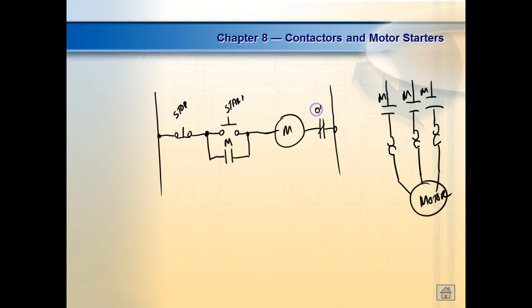And this right here would just be labeled OL for overload. So these sensors are what's controlling this contact right here. So I come up here, I start this thing, right? I press the start button, it seals in, the motor comes up and runs, right? And then if we get an overload, what's going to happen? These sensors are going to open this contact. And when this contact opens, it's going to drop out the circuit. And this is a really, really standard motor control circuit with a motor that has external overloads.